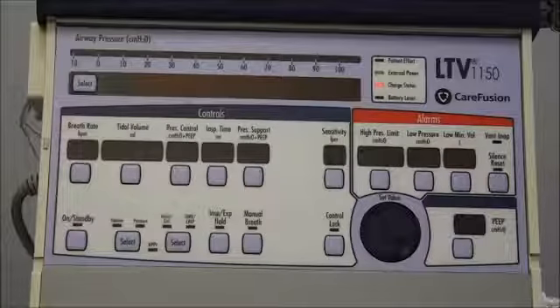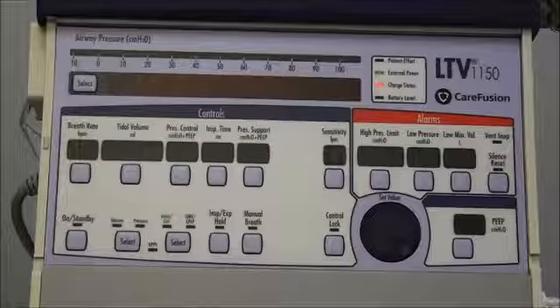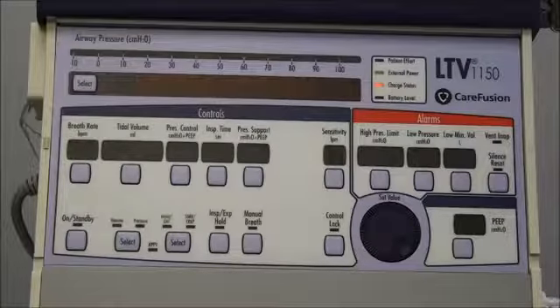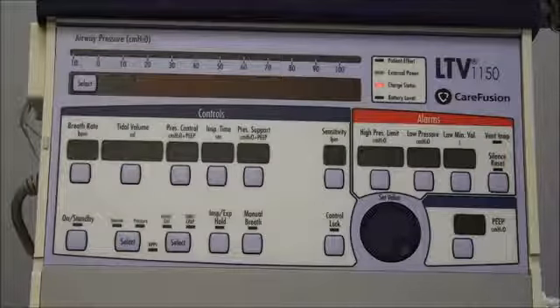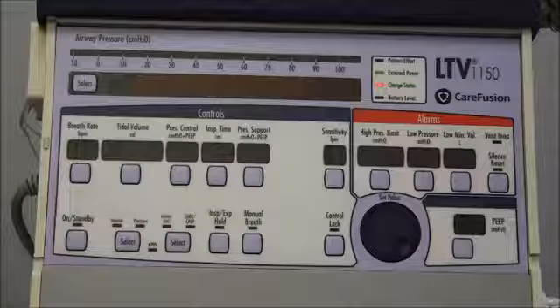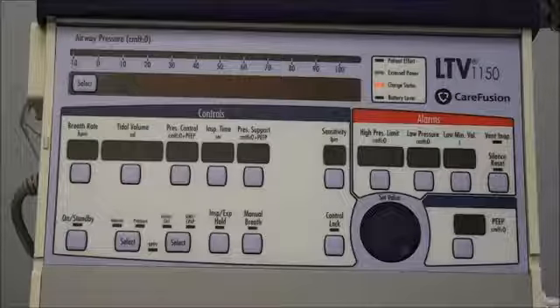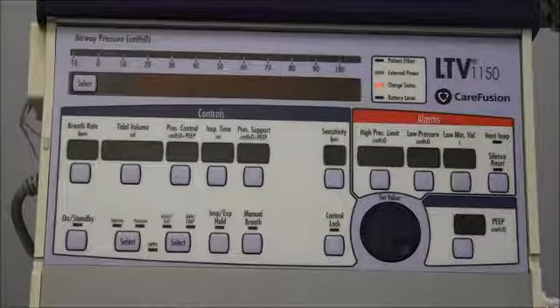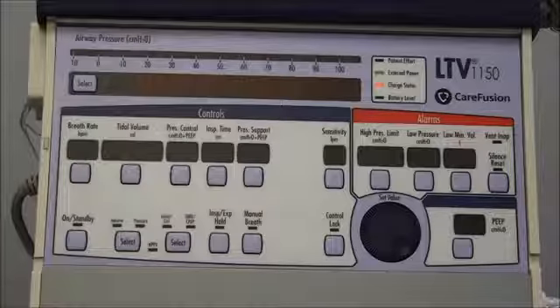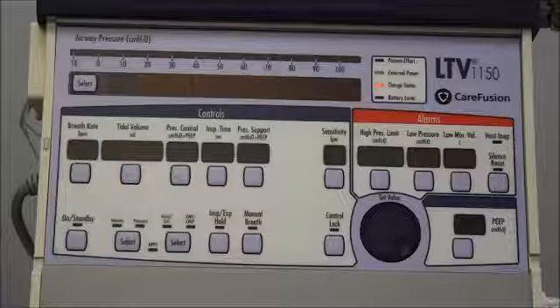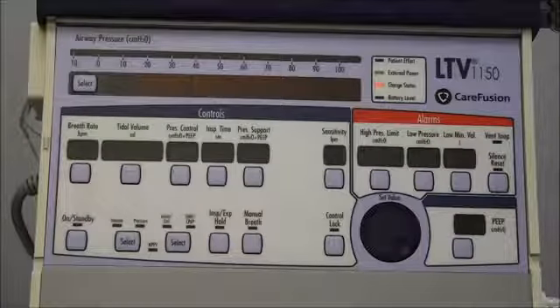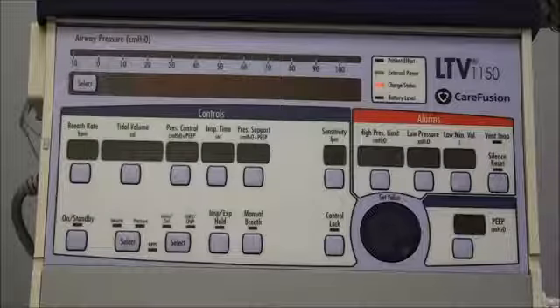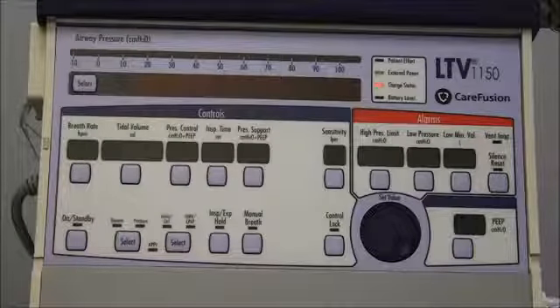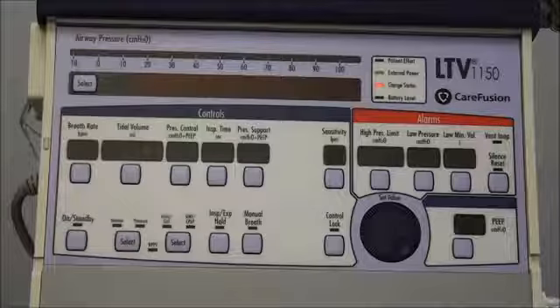Now, whenever you're transporting your patient or taking your patient out and away from anywhere where it can be plugged in, you always want to have another external power source, some sort of external battery. The internal battery should only be used for very short amounts of time and in an emergency situation, because your internal battery will only last about 45 to 60 minutes tops, and you never want to be depending on that if you're out and about. Of course, if you're just going to be moving your patient from room to room or in and out of bed, you can go ahead and use the internal battery, but you don't want to use it for any extended periods of time.